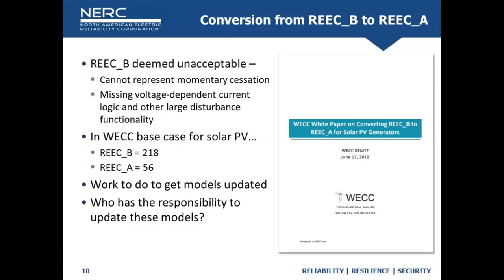Well, through all this analysis we've been doing as an industry over the last 2 years, we've realized that REECB really is not an acceptable model. It doesn't represent momentary cessation for those units it's applicable to, and it's missing some critical voltage-dependent current logic and other large disturbance functionality that limits its use. And every OEM I've talked to has stated they don't recommend using REECB anymore. So new interconnections have probably updated to using REECA for the time being.